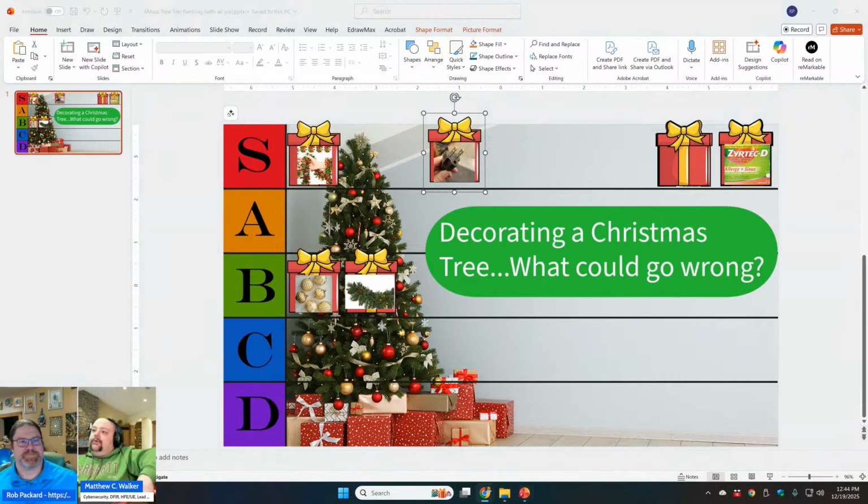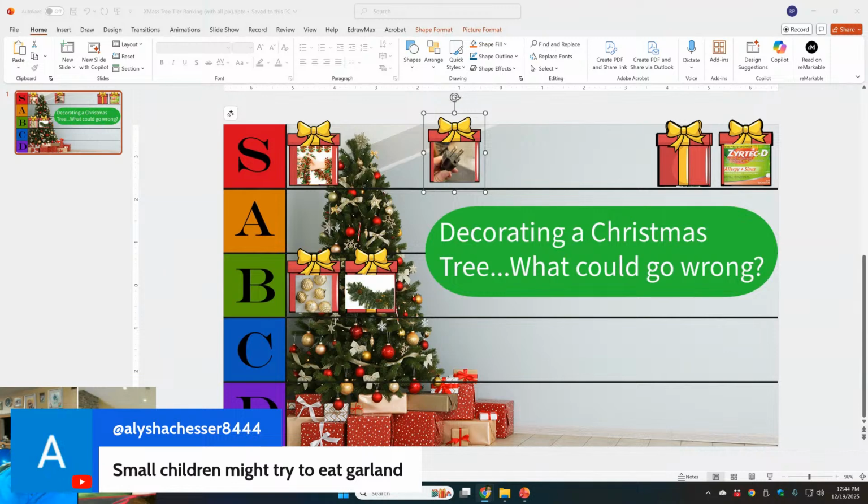Yep. And one of the other hiccups we look at with use errors is something called abnormal use, where the user does something completely unintended with the device. I think the wording is reckless use or intentional sabotage. It's abnormal use and outside of reasonable means of risk mitigation. So if we're messing with the ground wire or the ground plug, we're looking at potentials for electrical fires or shock hazards. And as a worst case scenario, I think those also go straight to that D category.